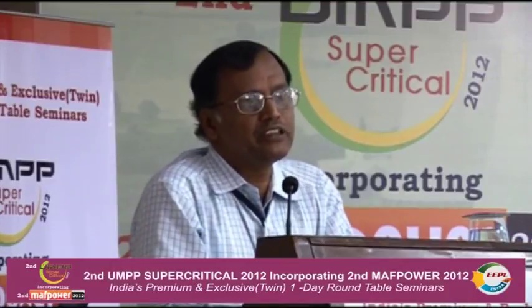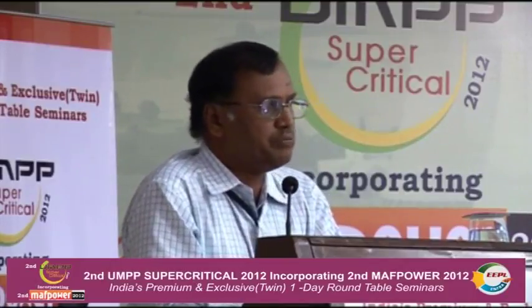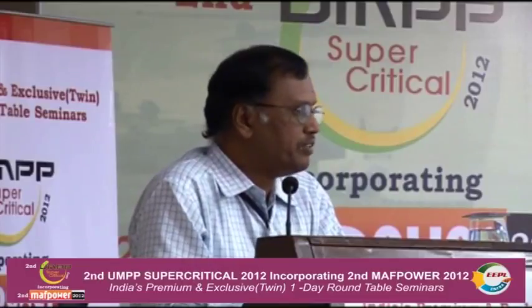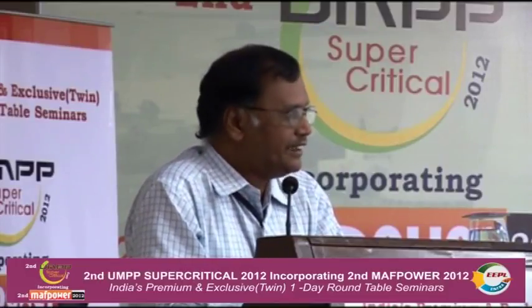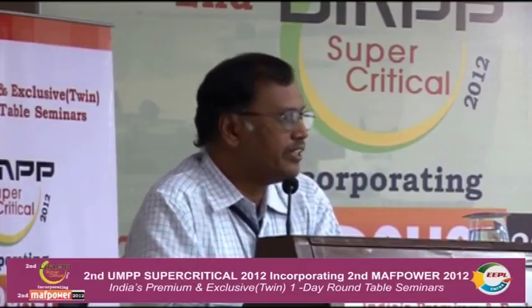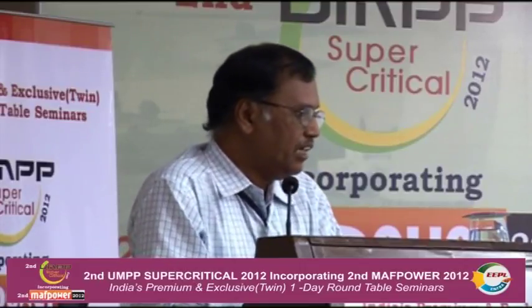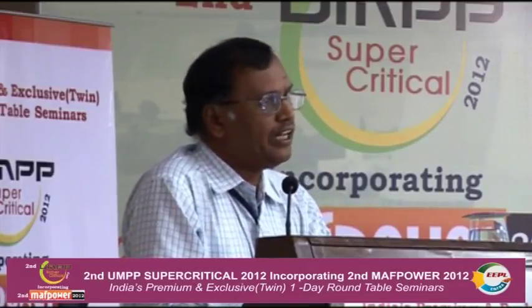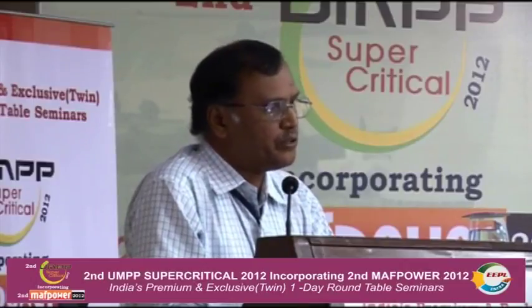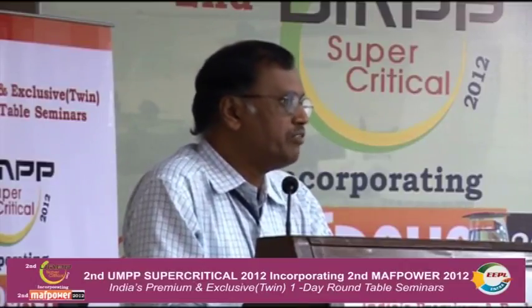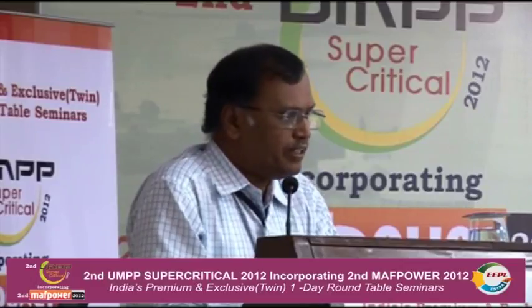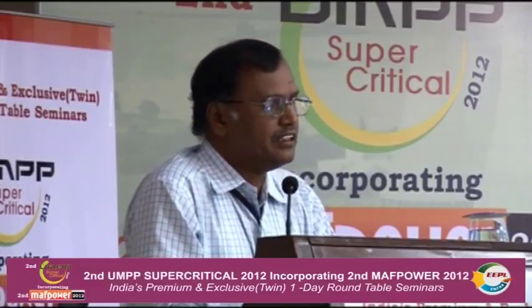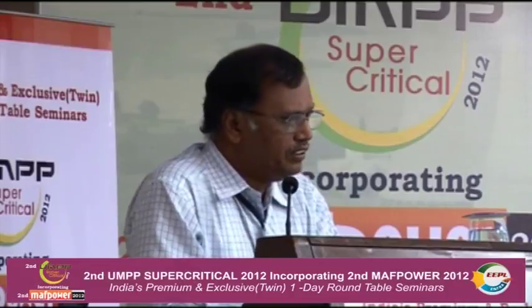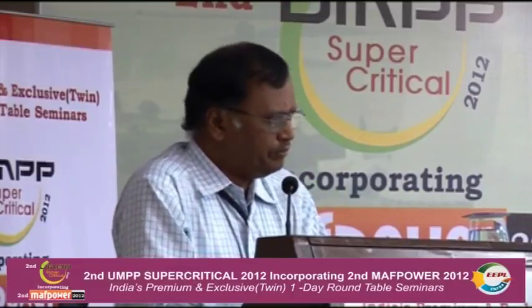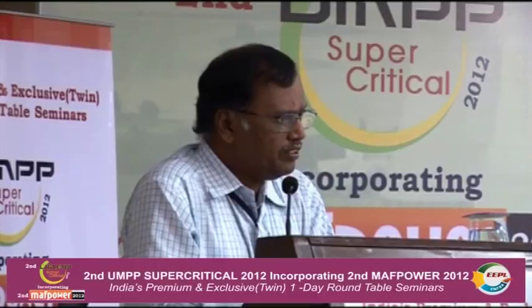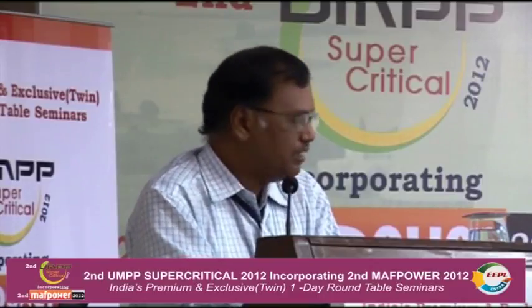Besides, we will be using smaller diameter tubes. Now we are using 2-inch tubes in 500 megawatts, and we will be going for still less than this, to have a better mass flux density. And obviously all these things lead to a higher pressure drop in the evaporator circuit. That is inevitable. That has to be borne by the feed water pump. But compared with the gain you are getting, that is acceptable. But again, because of the high pressure, all the components have to be sized for a supercritical boiler.